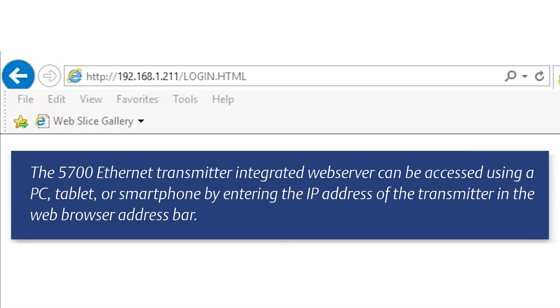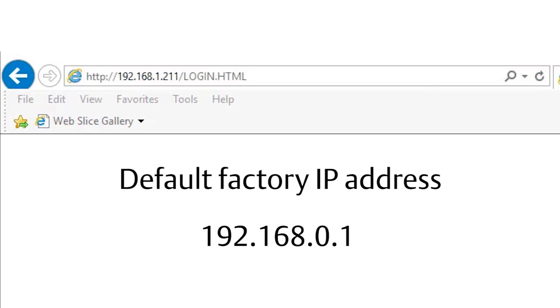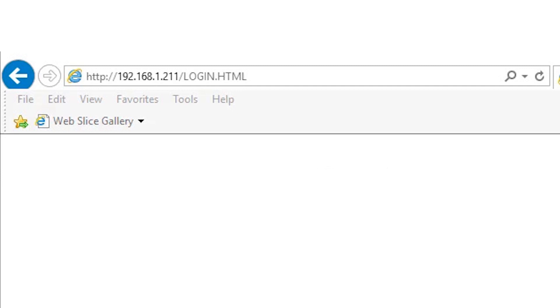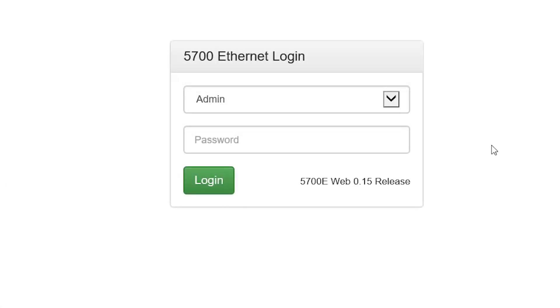The 5700 Ethernet transmitter integrated web server can be accessed using a PC, tablet, or smartphone by entering the IP address of the transmitter in the web browser address bar. The default factory IP address is 192.168.0.1. In this example the IP address has been changed from the factory default to 192.168.1.211. When the transmitter is found, the login page appears.